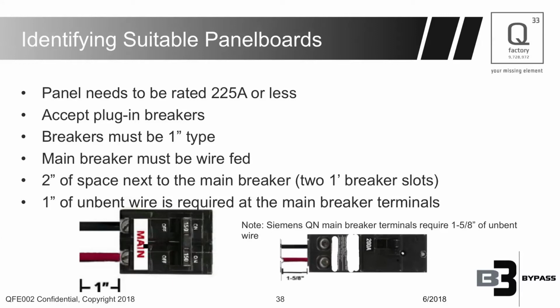One little side note here: on the Siemens QN, we'll need a little bit more space because the QN is recessed from the breakers, and so we need just over 1.5 inches for that one.